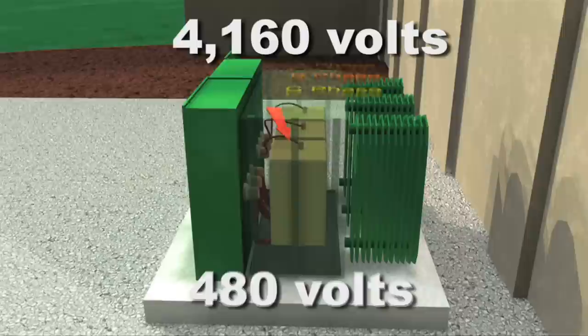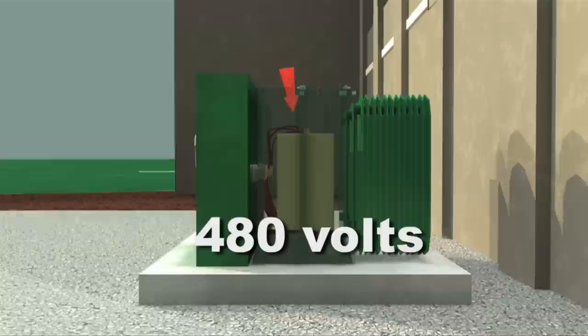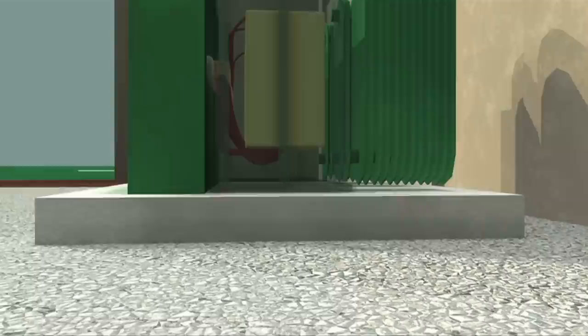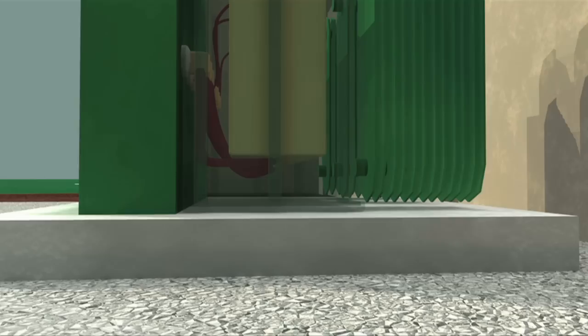The windings in this transformer will step down the voltage to 480 volts. Notice that the incoming wires that are carrying the 4,160 volts are smaller than the wires at the bottom carrying 480 volts. This is because the amperage increases when the voltage is lowered and vice versa. Higher amperage generates more heat and requires larger wires.